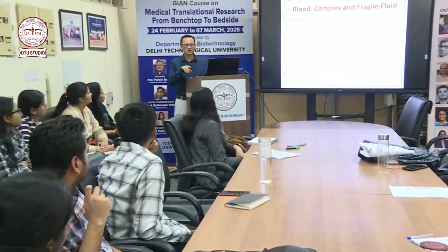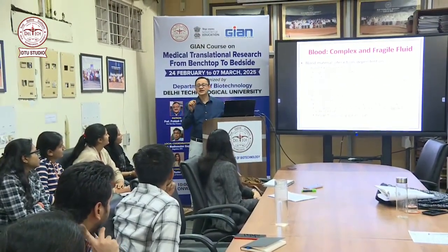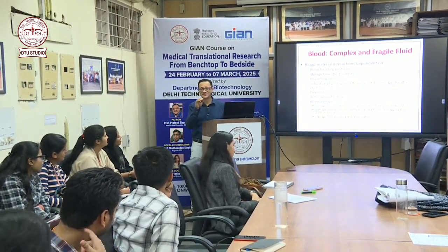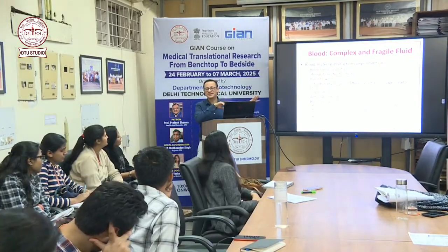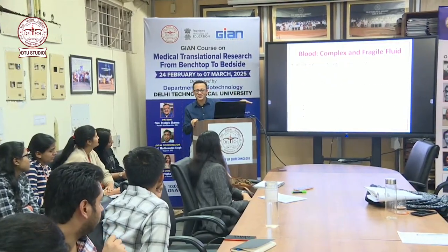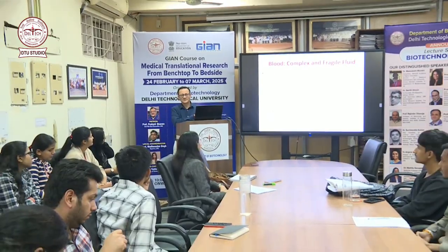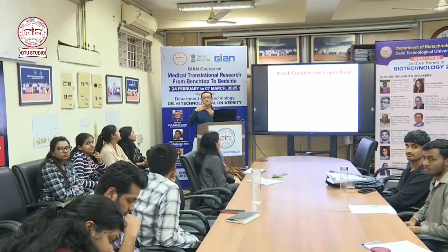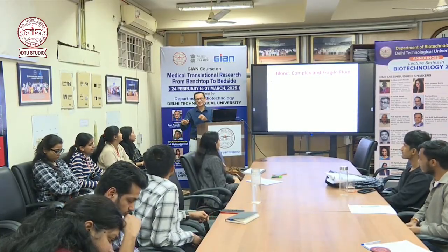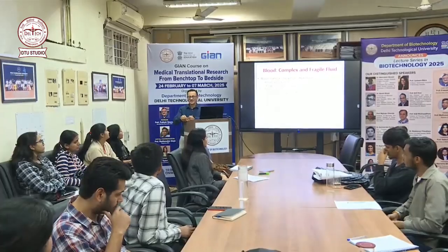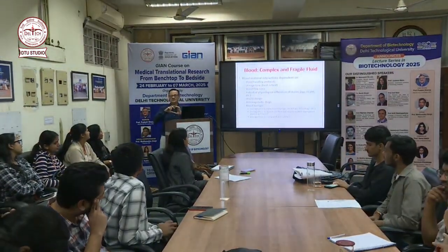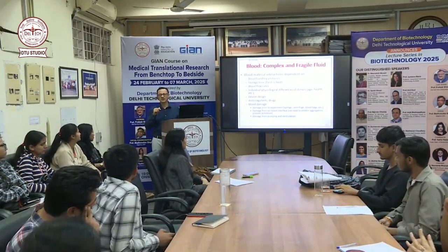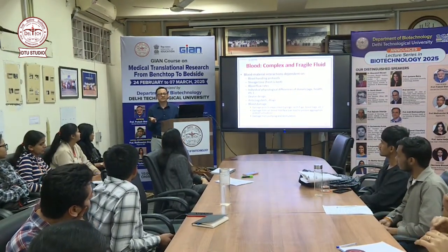Like the slide I showed you; I don't want to move, then it'll hang up again. The endothelium layer has all that prostacyclin, nitric oxide, heparan sulfate. That's what we are learning, biomimicry, right? We are learning what's there, what's preventing clotting, and we are making surfaces as close to that as possible. It's working, but it's still very challenging. You still have to make it work within those constraints of cost, sterilizability, storage stability. If you put a really amazing coating, but the coating cannot survive more than a day.